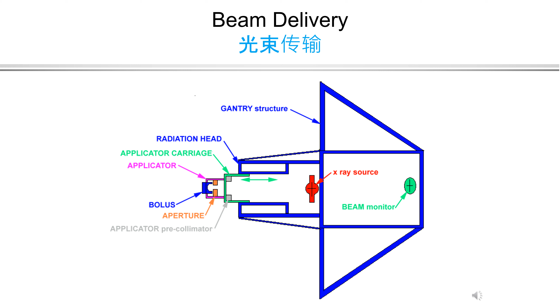The blue frame represents 1/8 of the structure of a rotating gantry. Attached to the gantry is the radiation head. A translatable applicator carriage is used to mount an applicator that holds beam shaping devices such as apertures and boluses as close as possible to the patient to minimize scatter and improve conformality and dose accuracy. Some systems, such as those that use the modulated scanning delivery technique, may not use an aperture but may incorporate a multi-leaf spot trimming collimator.